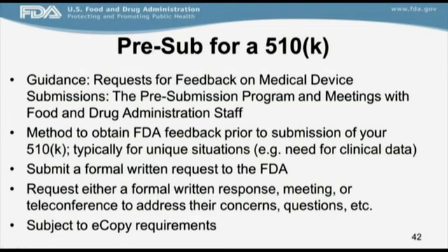But typically, a pre-sub for a 510K is only appropriate for unique situations, such as when you may need clinical data to support your demonstration of substantial equivalence. Through the pre-submission program, you would submit a formal written request to the FDA, and you would request either a formal written response, a meeting, or teleconference to address your concerns. Because this is a formal written request, it is subject to e-copy requirements, which we'll discuss during the submission of a 510K, but it's important to note that they are subject to e-copy.